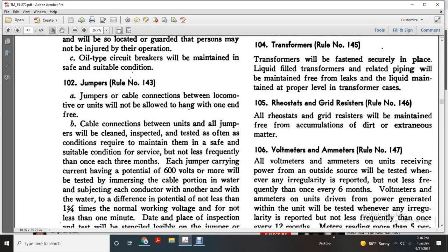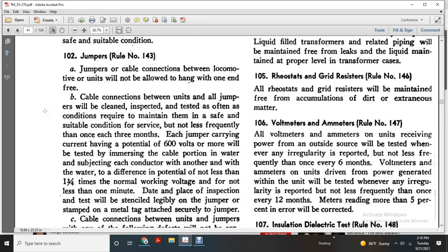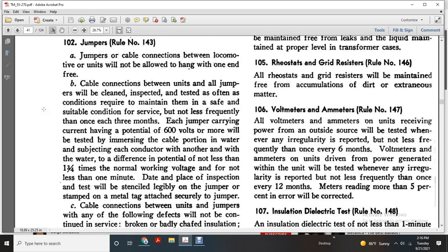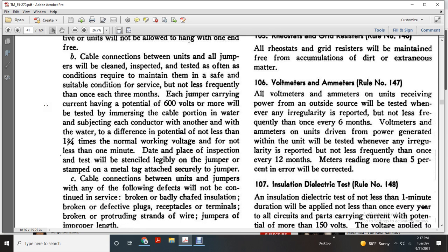All jumpers will be inspected and tested as often as conditions require to maintain them in suitable condition, and not less frequently than once every 3 months, especially jumpers carrying current with a potential of 600 volts or more. When tested by immersing the cable portion in water, a potential difference of not less than 1 3/4 times the normal working voltage will be applied between each conductor and the others for not less than 1 minute. The date of the inspection and testing will be legibly marked on a metal tag securely attached to the jumper.